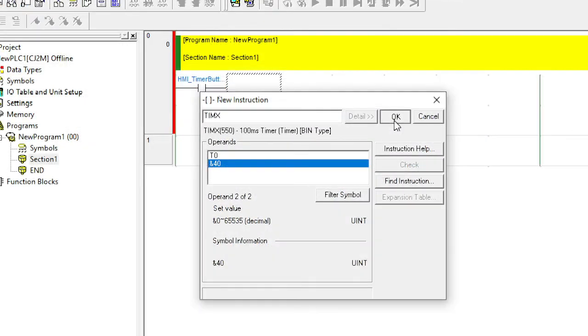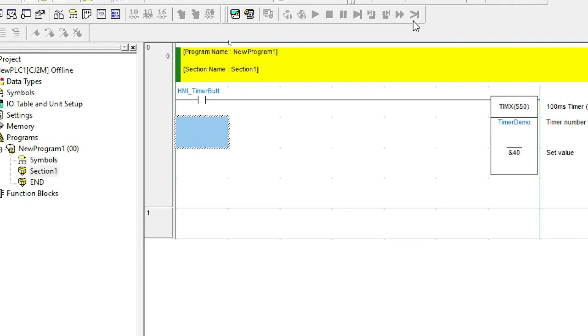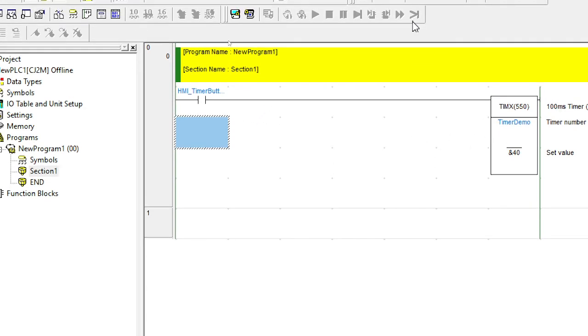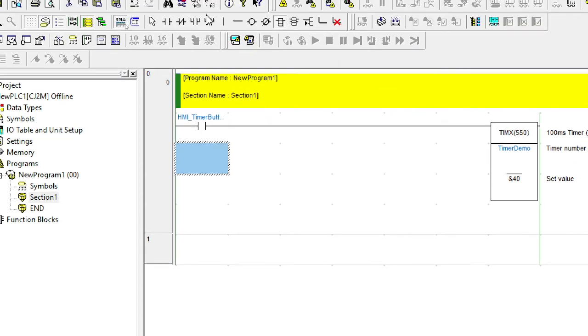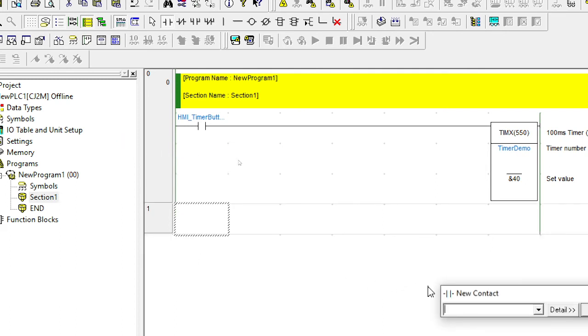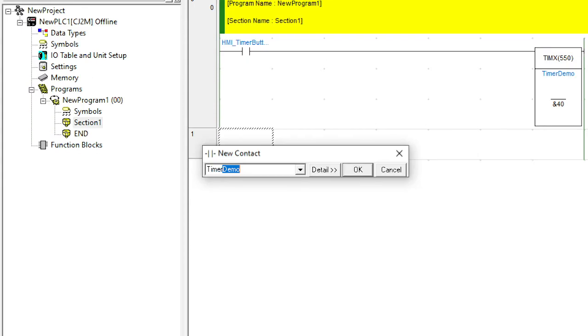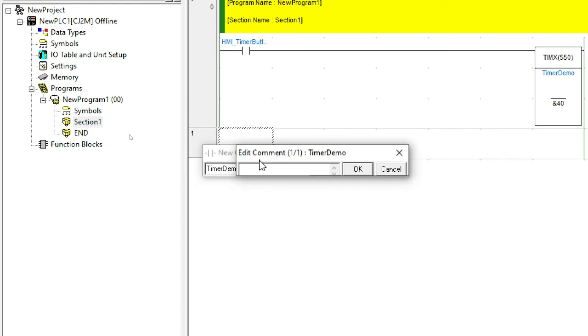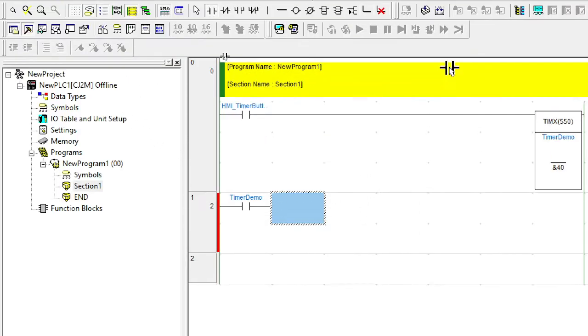And remember, this is available for all the functions. It does give a full implementation of the function there. And down the very bottom, there's even an example on how you can use it. Okay, so I'm going to select that now. And now I've added my first timer and it's going to run for four seconds. But I need the timer to do something. So what I want the timer to do is I want to turn on the lamp. So let me add in another contact here. In this case, we want to use the timer complete contact. So we know the timer ID was timer demo. So I'm going to go OK.